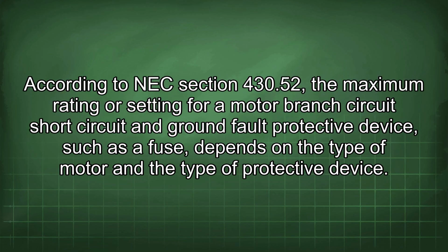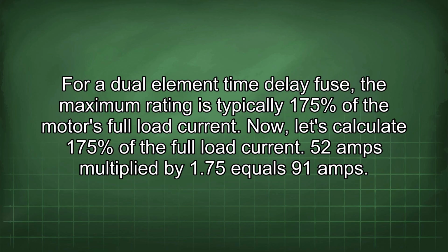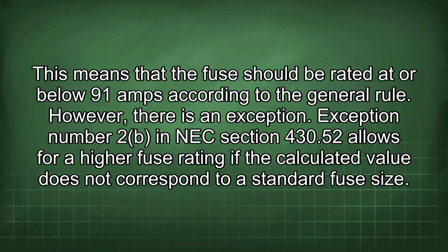According to NEC section 430.52, the maximum rating or setting for a motor branch circuit, short circuit, and ground fault protective device, such as a fuse, depends on the type of motor and the type of protective device. For a dual element time delay fuse, the maximum rating is typically 175% of the motor's full load current. Now, let's calculate 175% of the full load current. 52 amps multiplied by 1.75 equals 91 amps. This means that the fuse should be rated at or below 91 amps according to the general rule.